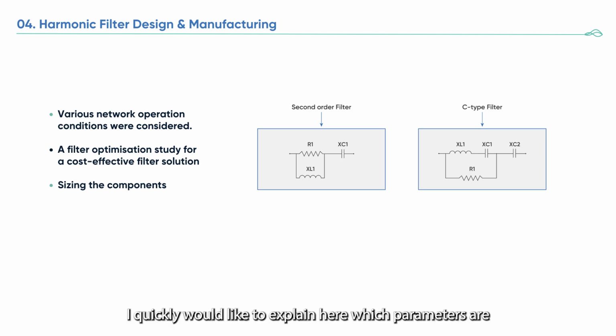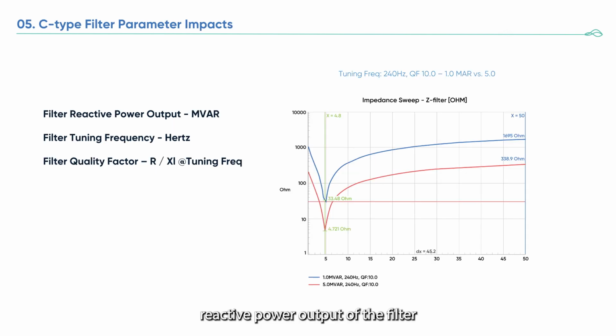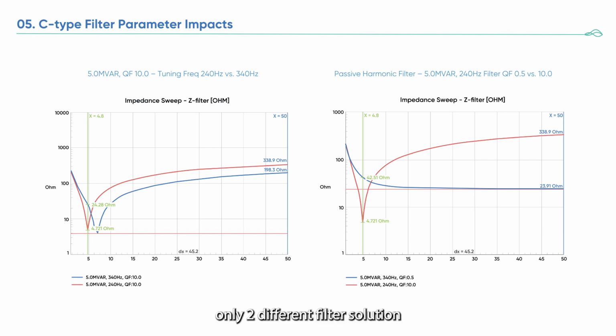And C-type filter parameters. I quickly would like to explain here which parameters are important for C-type filters. There are three main parameters: reactive power output of the filter, tuning frequency of the filter, and quality factor of the filter. In the right-hand side plots here, we have compared only two different MVAR size filters. All other parameters are identical, 1 MVAR versus 5 MVAR. When we increase the filter MVAR value, we reduce the filter impedance value. Generally, it provides better or more mitigation. The left-hand side shows only two different filter solutions, two different tuning frequencies. One of them is fifth order, the other one is seventh order. The fifth order filter provides better mitigation at fifth order. The seventh order filter provides better mitigation at seventh order.